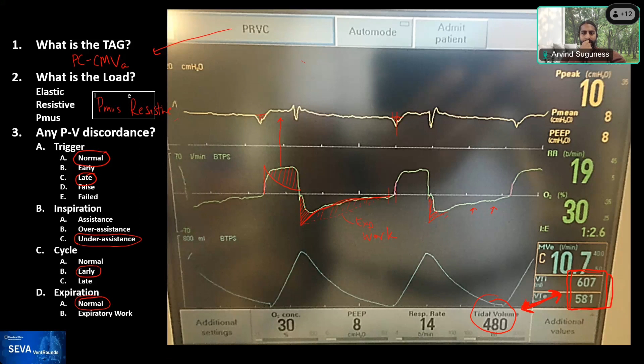Yeah, and so those deflections, like Dr. Mireles is drawing, should actually increase expiratory flow. If the patient is doing expiratory work, there should be a rounding and straightening out of that expiratory flow waveform, rather than the normal exponential decay like there is in this example. All right, good. Anyone have any other questions or thoughts here? The key idea when you're looking at the expiratory flow waveform is that anything that shifts the flow waveform in a positive direction is inspiratory work. Anything that pushes it in a negative direction is expiratory work. So in fact, we have some inspiratory work during the expiratory time, but no expiratory work is evident here, right?